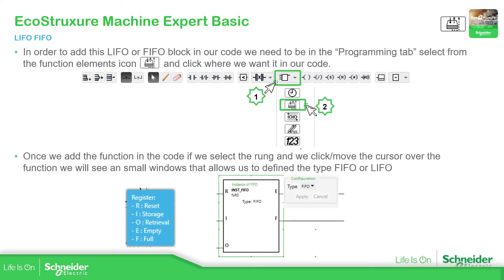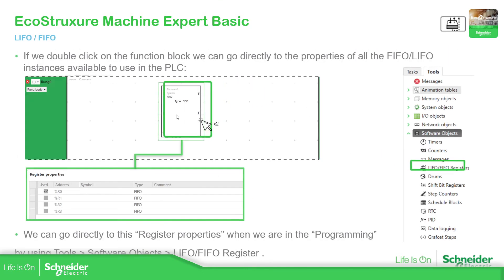In order to use the function block in code, it's very simple. We need to go to the function block icon and select it. Once we place it in our code, we have the possibility to configure FIFO or LIFO, and if we double click we can go to the FIFO LIFO properties. Moving around the function block we can see descriptions of inputs and outputs — you have the reset, storage, retrieve, and status outputs for empty or full. In the register properties you can configure whether you want LIFO or FIFO.